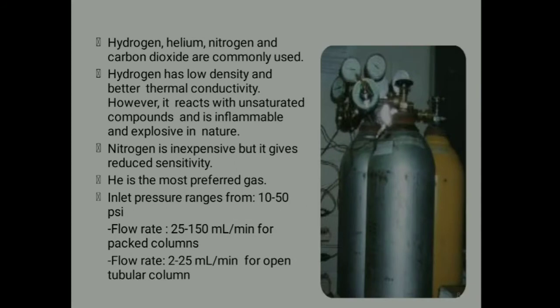Hydrogen, helium, nitrogen, and carbon dioxide are commonly used carrier gases. Hydrogen has low density and better thermal conductivity; however, it reacts with unsaturated compounds and is inflammable and explosive in nature. Nitrogen is inexpensive but gives reduced sensitivity. Helium is the most preferred one. Inlet pressure ranges from 10 to 50 psi. Flow rate is about 25 to 150 ml per minute for packed columns, and around 2 to 25 ml per minute for open tubular columns.